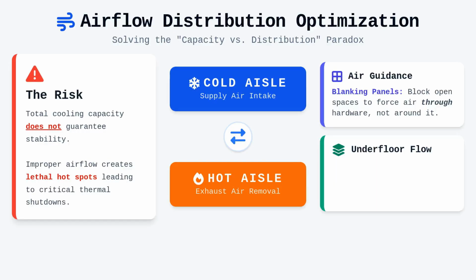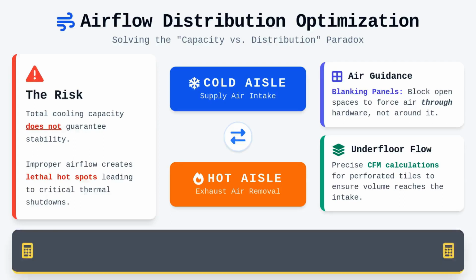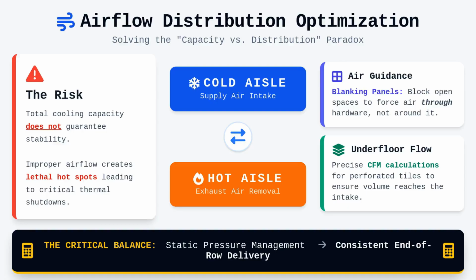Furthermore, in environments utilizing raised floors, we must calculate the necessary cubic feet per minute flow rates to ensure that perforated tiles deliver the required volume to the intake side of the equipment. These calculations often involve a delicate balance of static pressure management, as excessive pressure loss under a raised floor can lead to suboptimal delivery at the end of the supply rows.